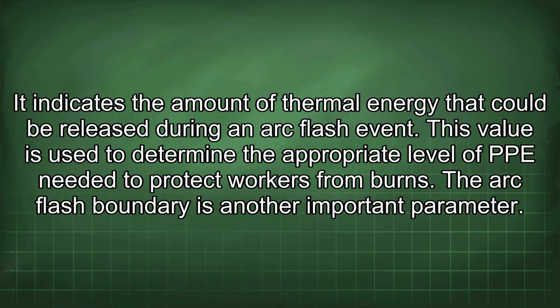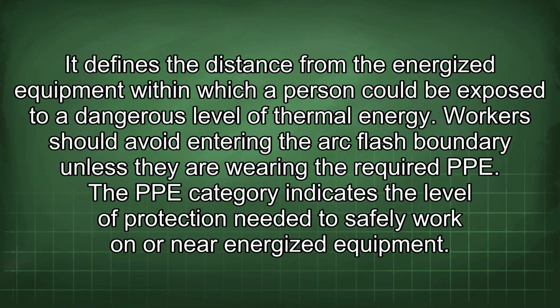The incident energy is a critical parameter on the label. It indicates the amount of thermal energy that could be released during an arc flash event. This value is used to determine the appropriate level of PPE needed to protect workers from burns. The arc flash boundary is another important parameter. It defines the distance from the energized equipment within which a person could be exposed to a dangerous level of thermal energy. Workers should avoid entering the arc flash boundary unless they are wearing the required PPE.